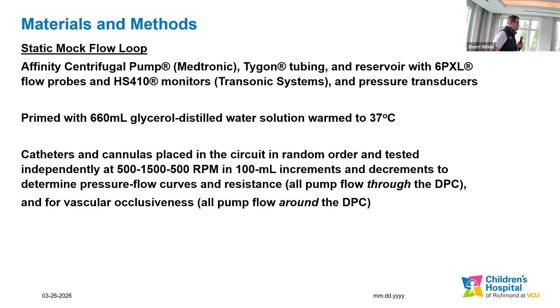the distal perfusion cannula. So this is the schematic of their circuit setup, again with the direct testing of catheter resistance with all the flow going through either the introducer sheath or the pediatric arterial cannula, and then with the catheter or cannula clamped off and all the circuit flow going around the catheter or cannula. So they were able to determine both the resistive component and the obstructive component of each of these devices.